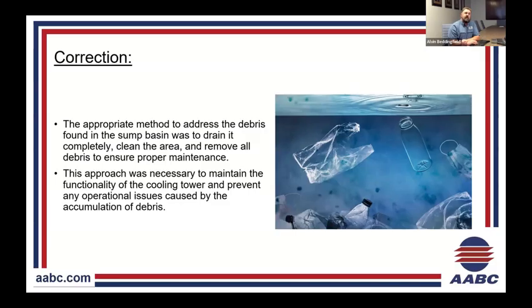So the only appropriate method to address this debris found in the sump basin was to completely drain it and clean the area, removing all the trash bags. Upon assistance from mechanical, they ran the pumps a little bit, opened up the strainers, and let that blow out into the mechanical yard, and by doing so they pulled the strainers at the same time to clean them. I ended up pulling out, to my estimate, I wish I had a picture of it, about 35 bags of HEB, just the grocery sacks, and a few water bottles. Obviously, those alone aren't going to cause that, but it was basically sandwich bags, Walmart bags, just all within that debris.